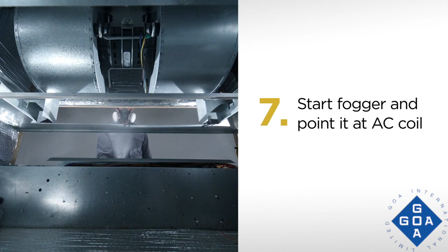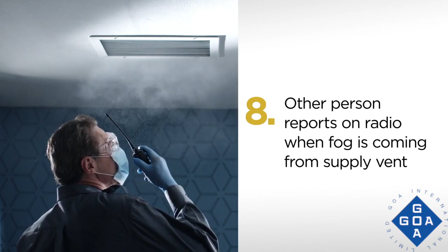Seven, start the fogger and point it at the AC coil. Eight, as soon as the other person sees fog coming from the supply vent, they report this on the radio. Nine, immediately stop the fogger. Ten, let the AC system run for 5 minutes to clear out the ducts.